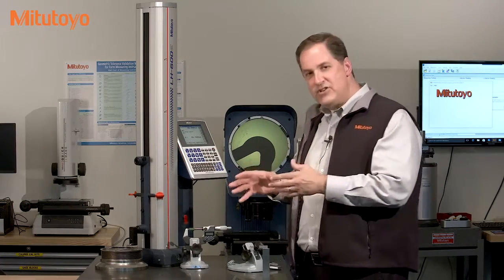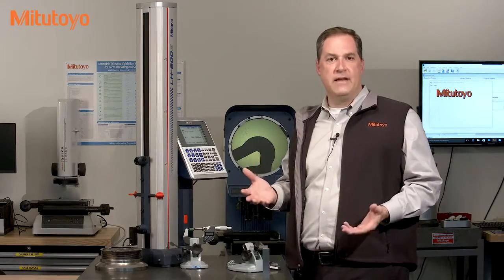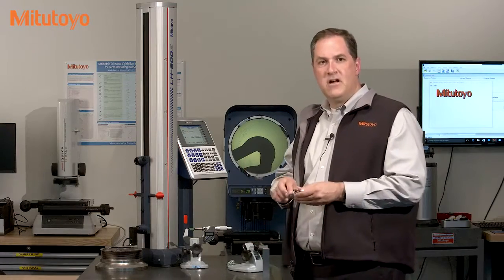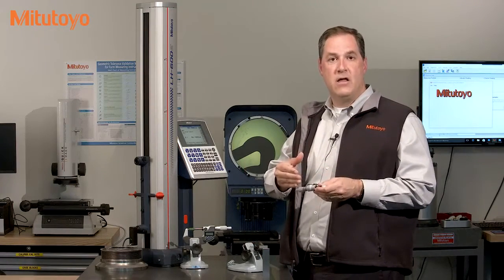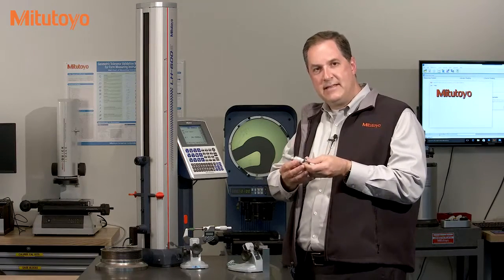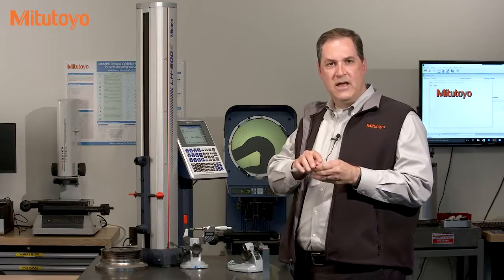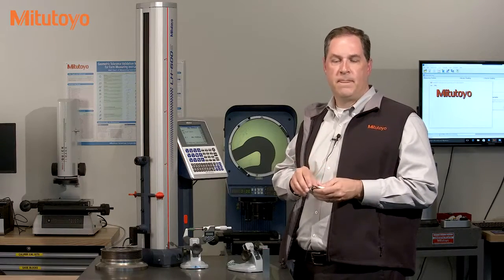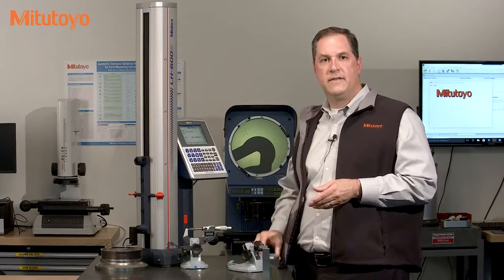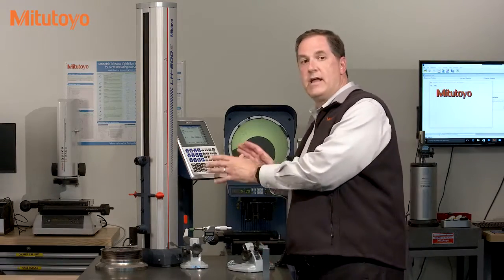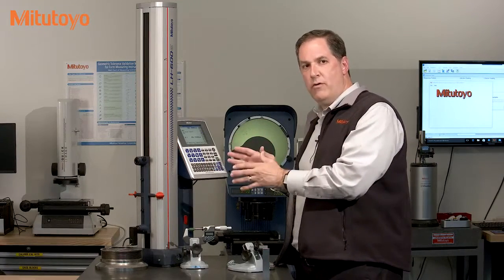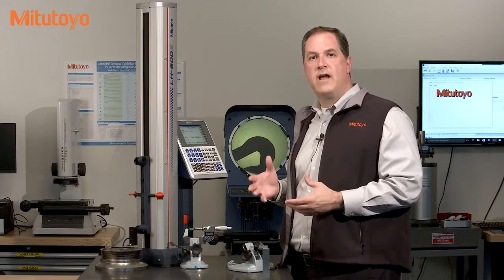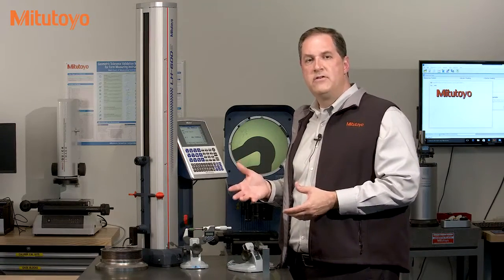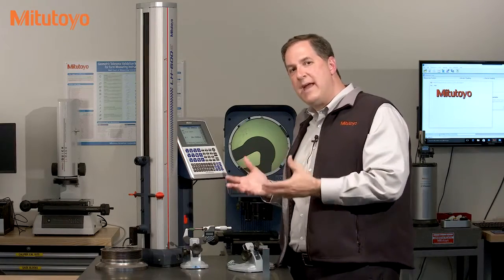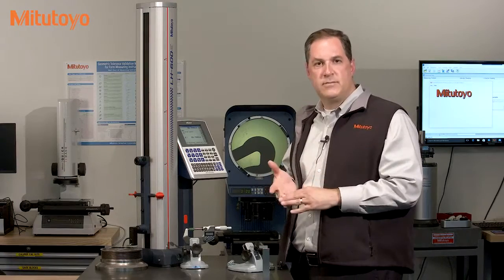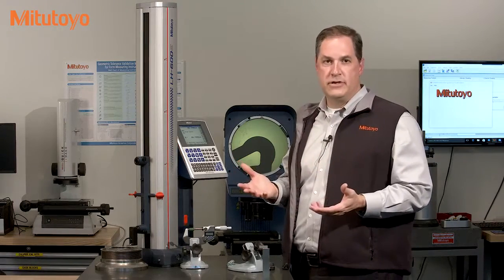Now third, if the gauge is out of tolerance, what can be done to fix that? For some equipment, like this micrometer, a good cleaning is often enough to bring it back within tolerance. After the as found data is collected, it is typical in calibration to clean and perform any recommended preventive maintenance. After that's done, in some cases, like in digital measuring equipment, like this linear height gauge, there is some type of maintenance mode that authorized technicians can access that provides for corrections or adjustments to be made to the accuracy of the instruments. And in some cases, cleaning, maintenance, and adjustments are not enough, and then repair is usually needed.